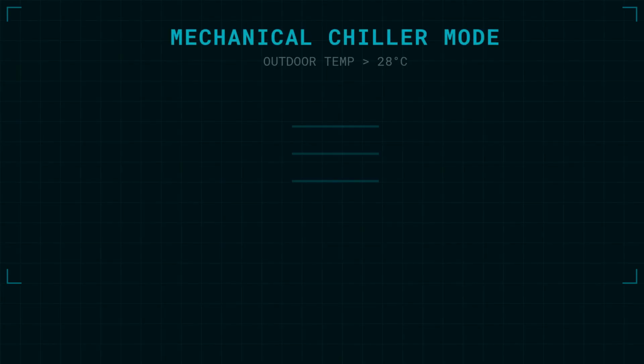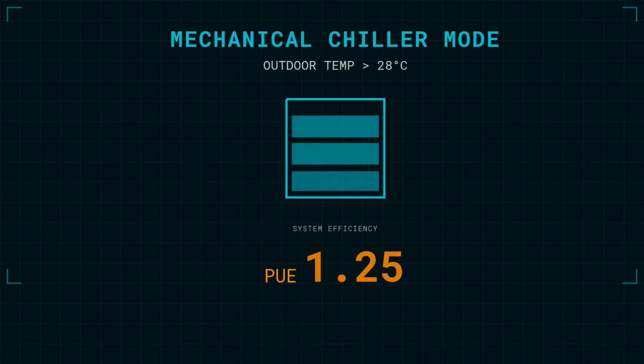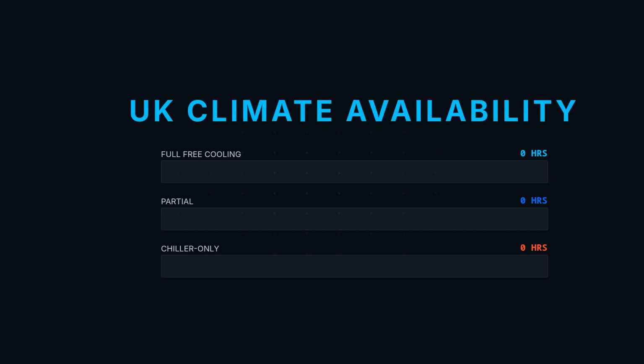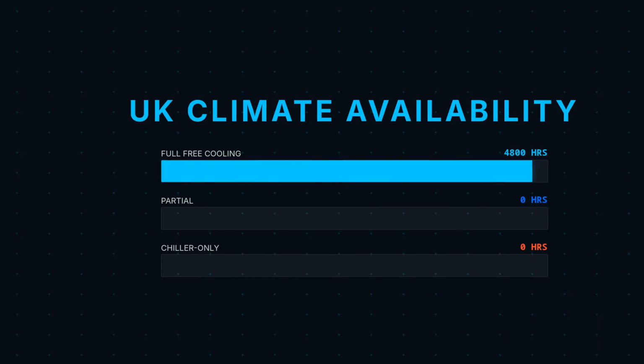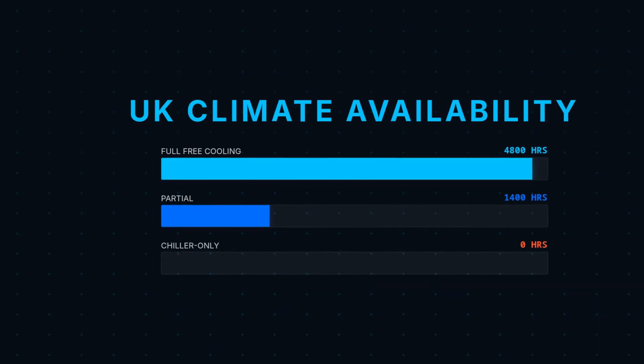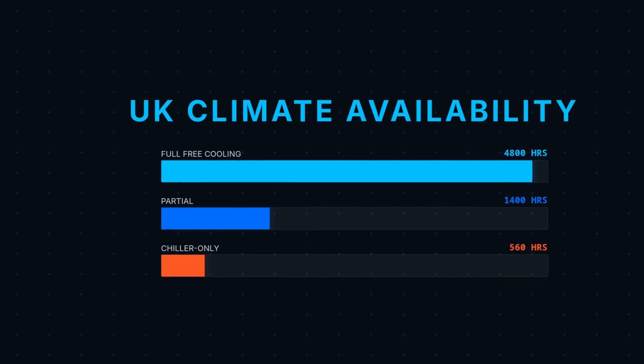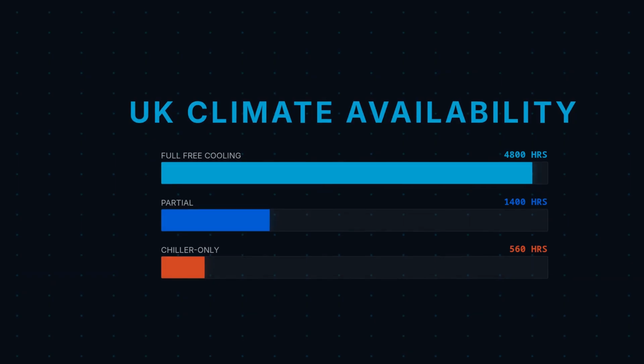On the warmest days, exceeding 28 degrees, the economizer dampers close completely. The system enters full mechanical chiller mode. In these peak conditions, the PUE rises to approximately 1.25 to maintain hall stability. In the UK climate, we benefit from over 6,200 hours of free cooling per year. Mechanical chillers are on duty for only 560 hours. This is the engineering data that underpins our weighted average PUE target.